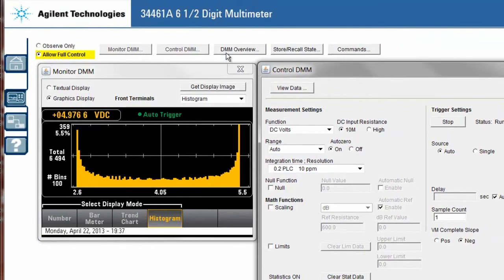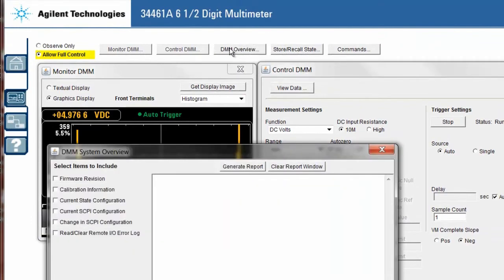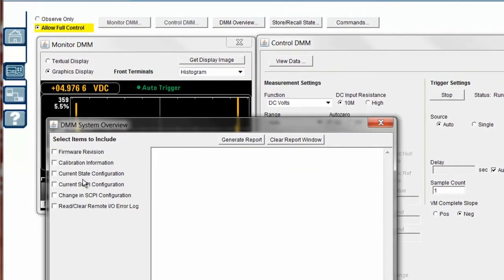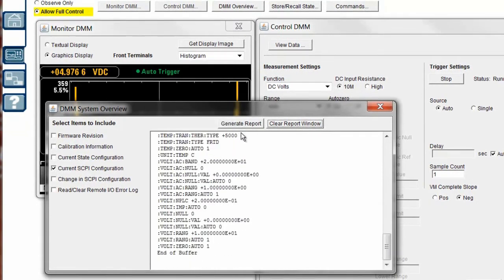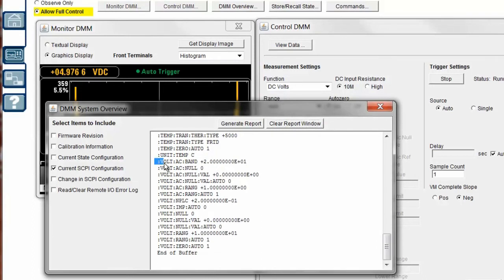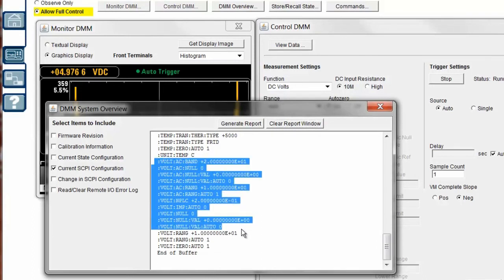So programmers will also really like the web UI in that you can actually bring up the SCPI commands that are being generated by the web UI. So from here, you can just go in and cut and paste the SCPI commands and put it into your own program.